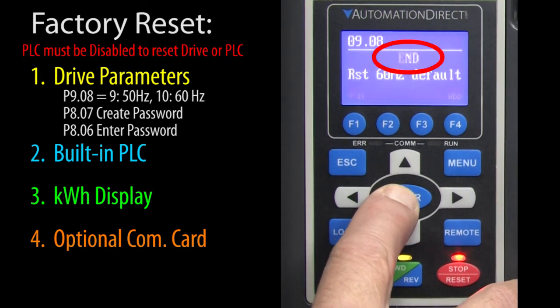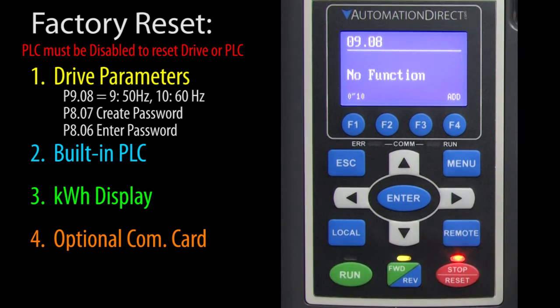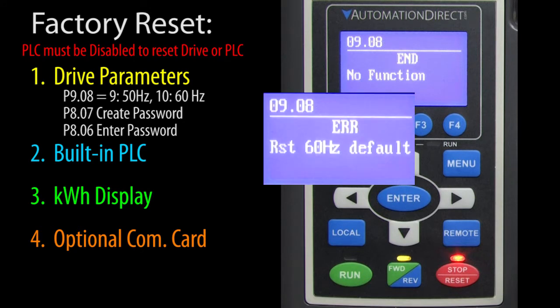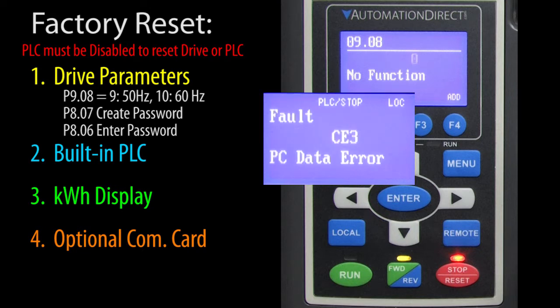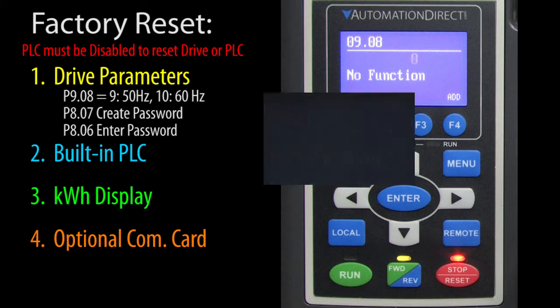If I press Enter, I see an end, which tells me all of the drive parameters were reset to factory default. Now, if the reset didn't work, you'll get a brief error message on the screen. For most parameter entry operations, it's easy to miss that because they're both 3 letters and they both begin with the letter E. So watch that closely when you're entering parameters. Fortunately, for the reset operations, it's kind of hard to miss because the display also frantically flashes at you until you press the stop button to clear the error.